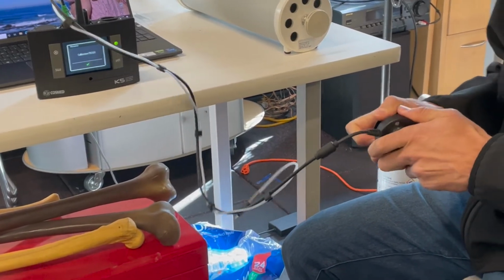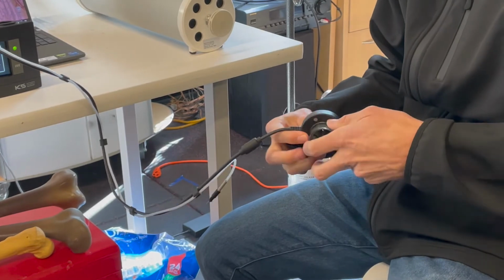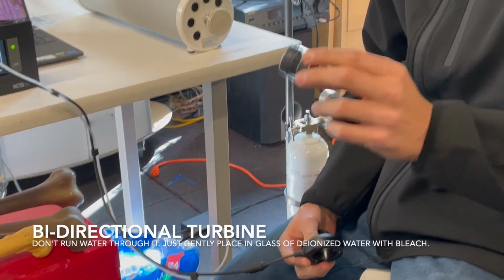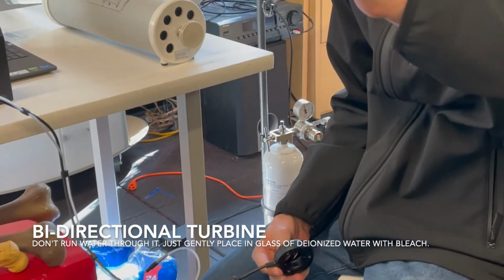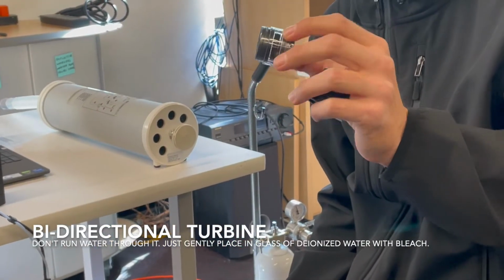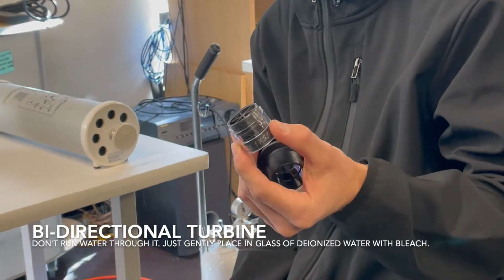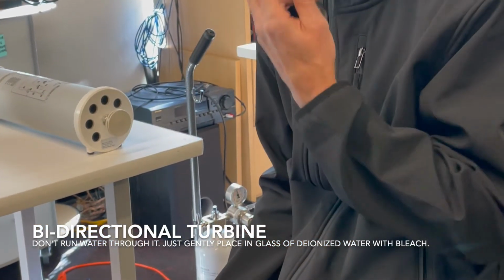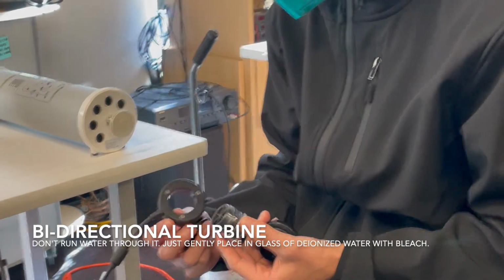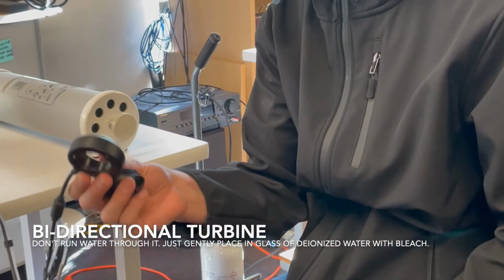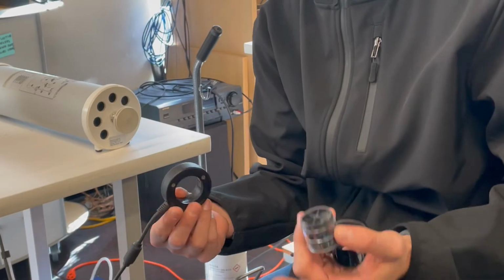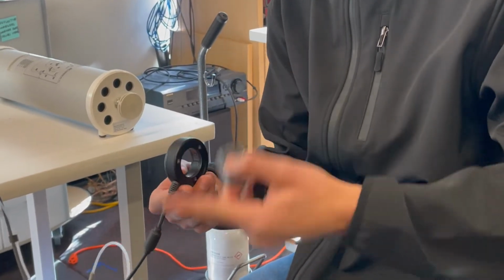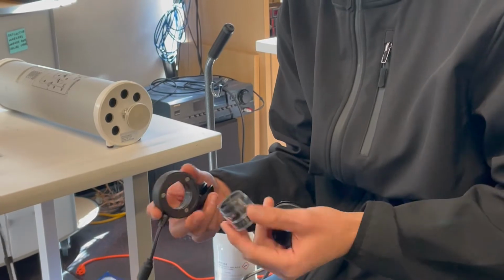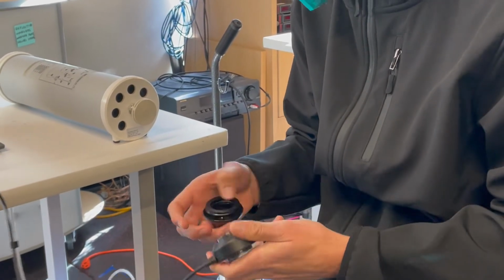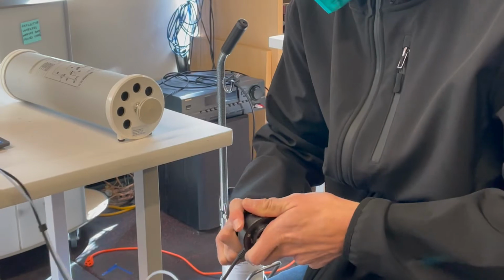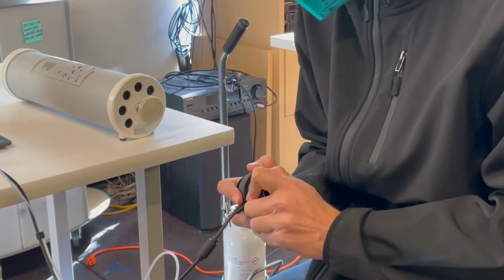Just to explain a little more on the turbine, I know you're probably already familiar with it, but it's a bidirectional digital turbine. It's got a little fin in there and it's able to measure ventilation based on the revolutions per minute, and the direction of spin tells it whether it's inspiring or expiring. And this is the actual reader. It's got photo receivers and light diodes, and the light gets interrupted, and that's how it knows it's spinning in a certain direction. So that's pretty straightforward.